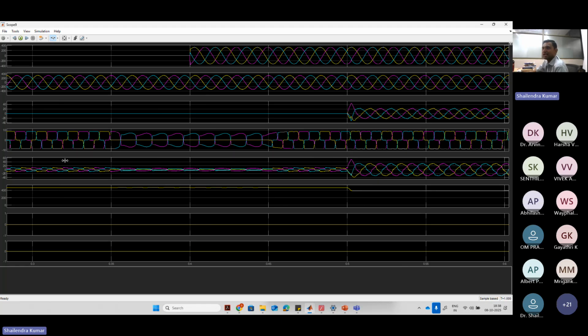And here the inverter is supplying the fourth signal, which is the VSC current. You can see that as long as we have standalone operation, only the standalone power or the load power required by the load is supplied by this inverter. However, the moment the grid appears, your VSC current increases because now it is operating in MPP mode.